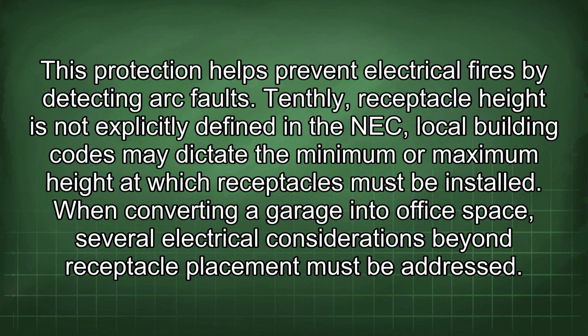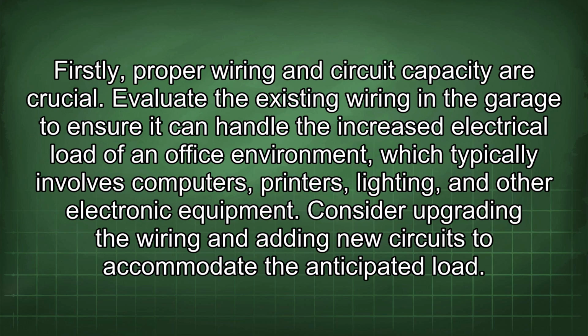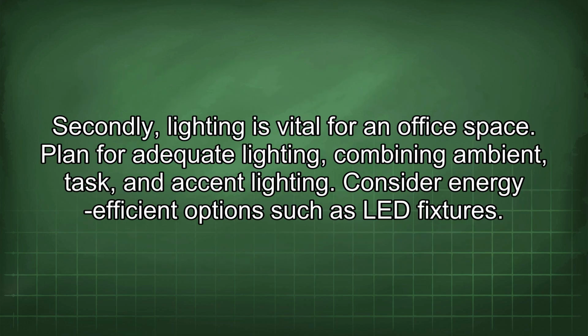When converting a garage into office space, several electrical considerations beyond receptacle placement must be addressed. Firstly, proper wiring and circuit capacity are crucial. Evaluate the existing wiring in the garage to ensure it can handle the increased electrical load of an office environment, which typically involves computers, printers, lighting, and other electronic equipment. Consider upgrading the wiring and adding new circuits to accommodate the anticipated load. Secondly, lighting is vital for an office space. Plan for adequate lighting, combining ambient, task, and accent lighting. Consider energy-efficient options such as LED fixtures.